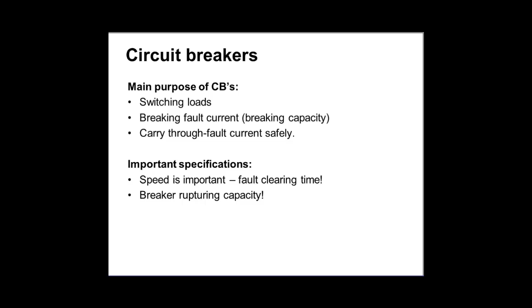All I'm saying is that fault clearance time is important. So if someone asks you what is the fault clearance time, you would say, well, if you're talking about fuse operation, easy. The time it takes for the fuse link to melt down. What about relay protection? Well, according to the relay settings, once the fault occurs, first, it will take some time for the relay to operate. Okay, so can I say the fault is cleared? Nope. I said the relay is operated.